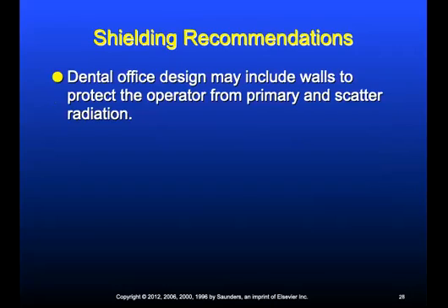If there isn't a wall, like a gypsum wall or a lead wall, in between you and the X-ray, let's say your patient is situated next to a hallway, you'll just want to make sure that there is nobody standing between 5 to 8 feet, or at least 6 feet, away from the source of radiation.